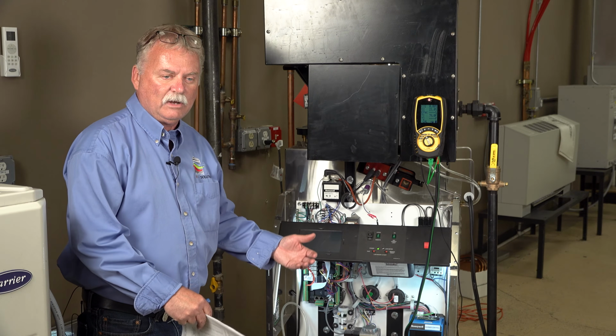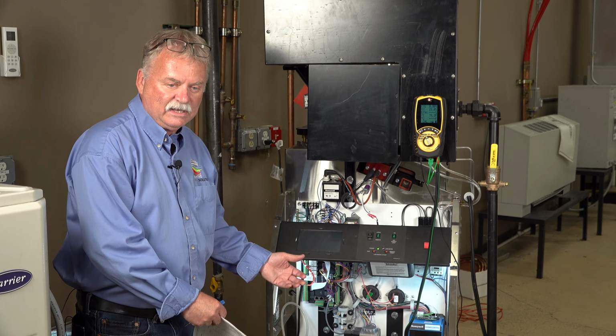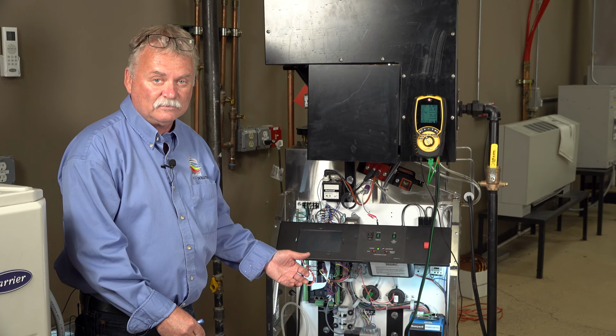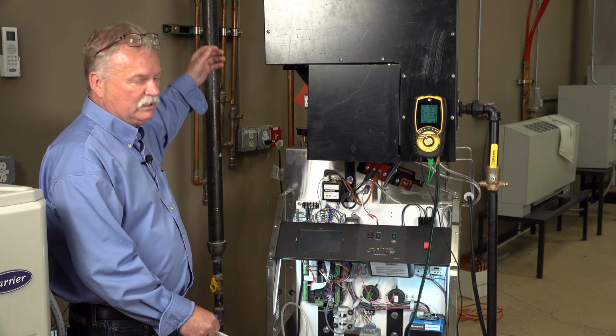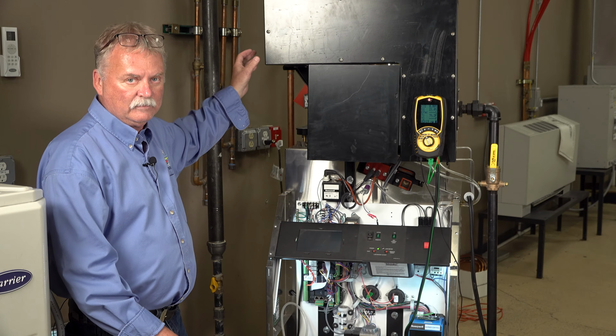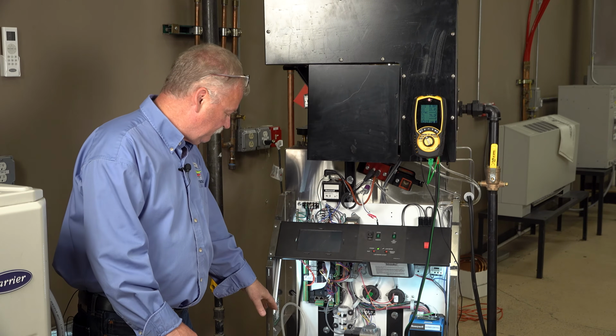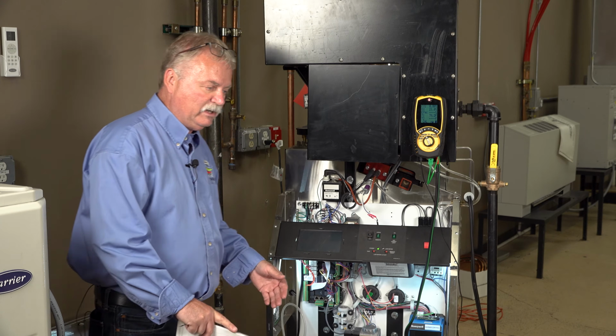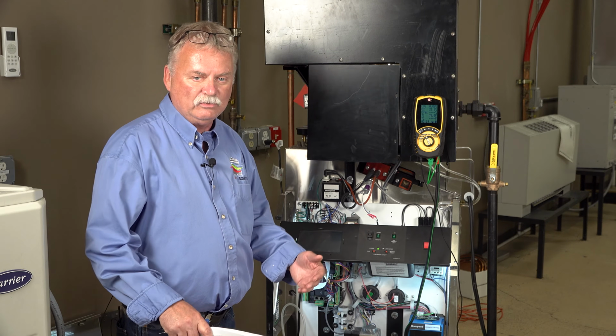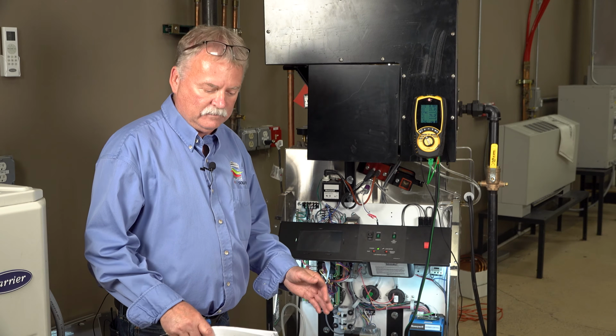basically dealing with the city's gas supply. This is the gas pressure they're giving us. This is what we have to use. If you had high gas pressure, you would be adjusting at your pressure regulator. But since we have what we want, we're going to start going in, looking and seeing what the boiler is doing now before we touch anything.